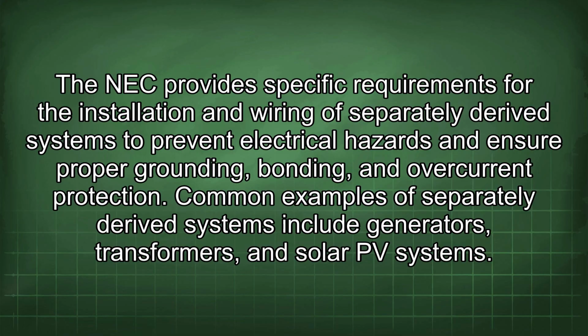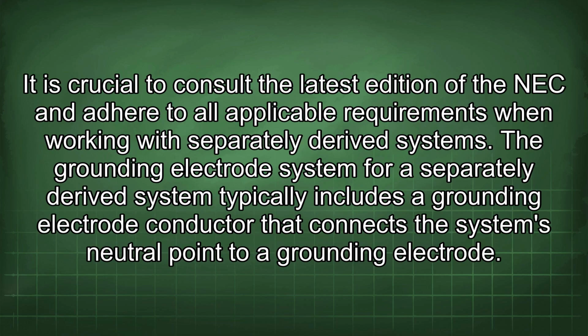Common examples of separately derived systems include generators, transformers, and solar PV systems. It is crucial to consult the latest edition of the NEC and adhere to all applicable requirements when working with separately derived systems. The grounding electrode system for a separately derived system typically includes a grounding electrode conductor that connects the system's neutral point to a grounding electrode.